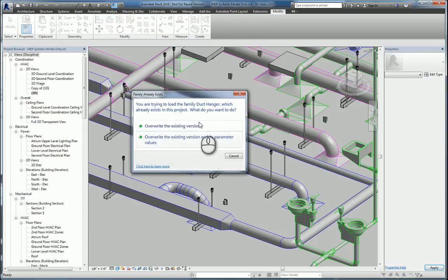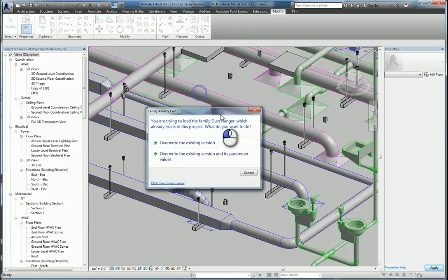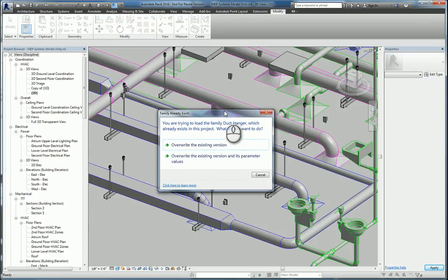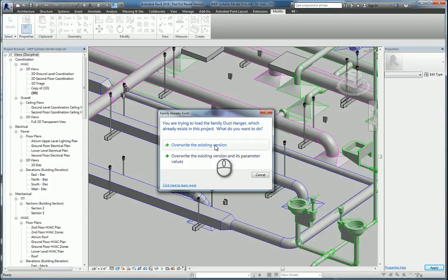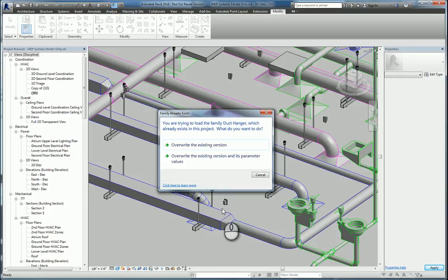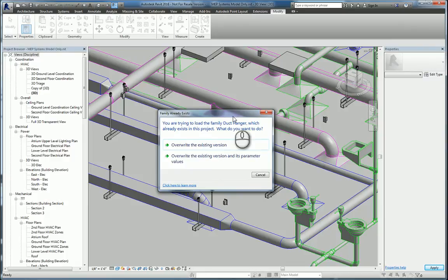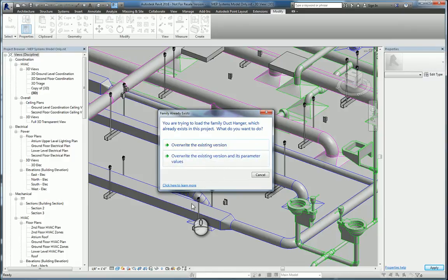Now when it comes up to this window to replace the existing one, if you pick the first one, it will replace the families with the new one, but it won't alter any modified instance properties values for each of these hangers, because remember, these Duct Hangers, they're different widths. So if you were to pick the top one, you're okay. If you pick the bottom one, all of them will default back to the original design of that family.